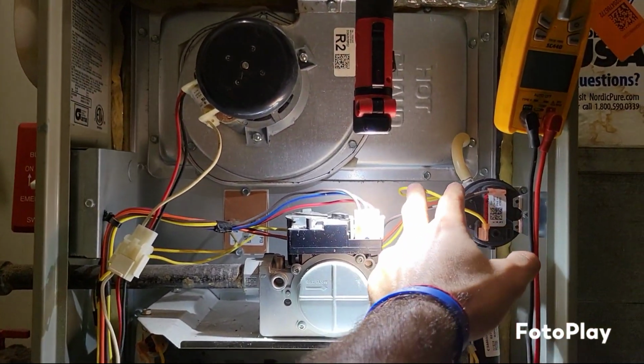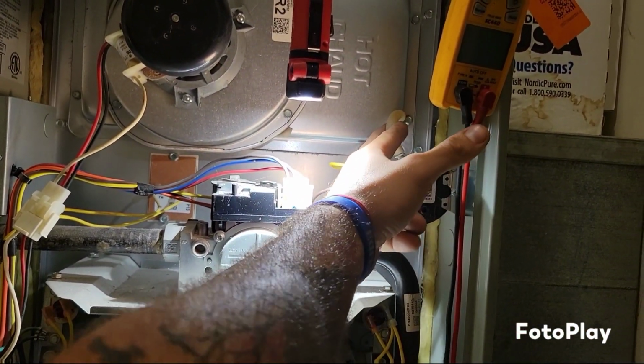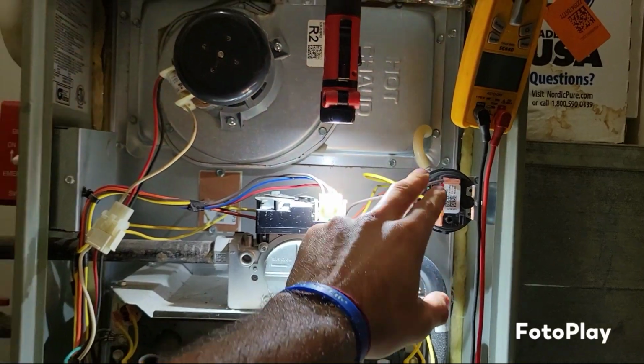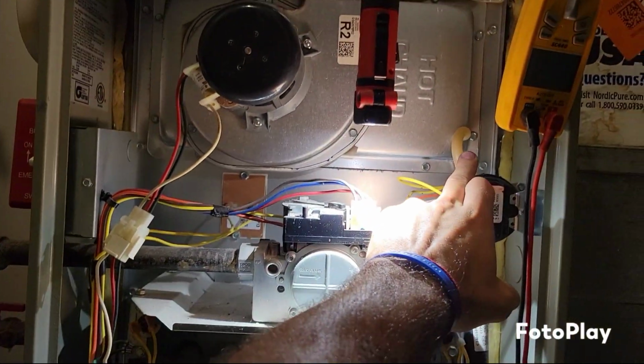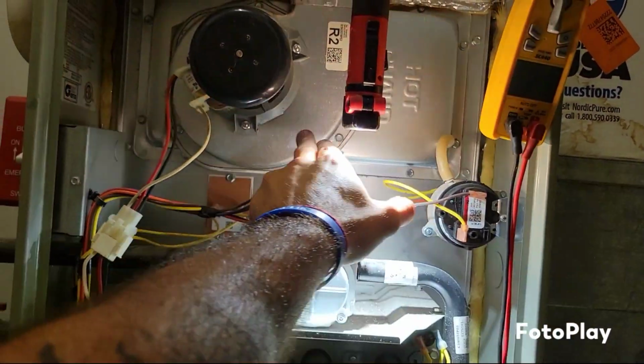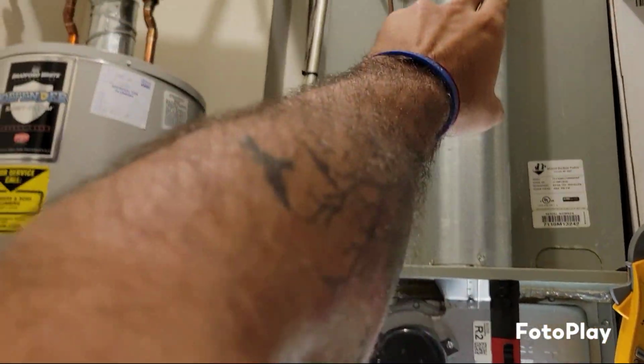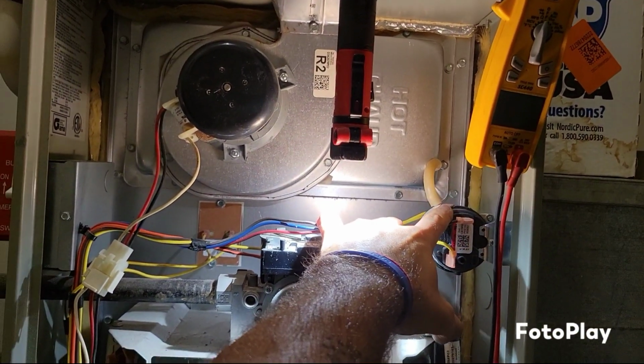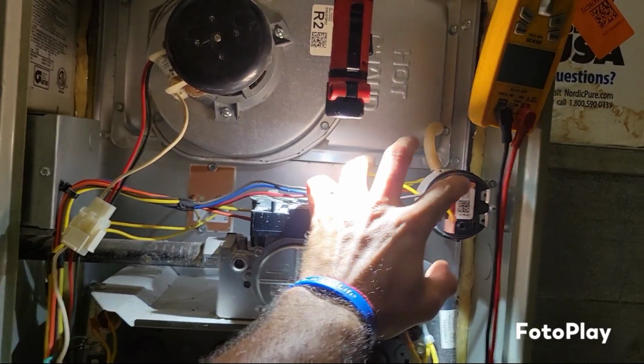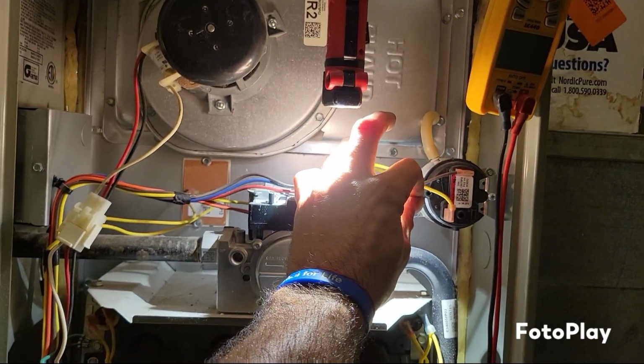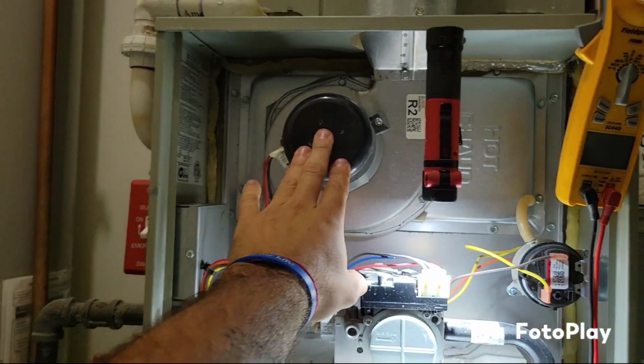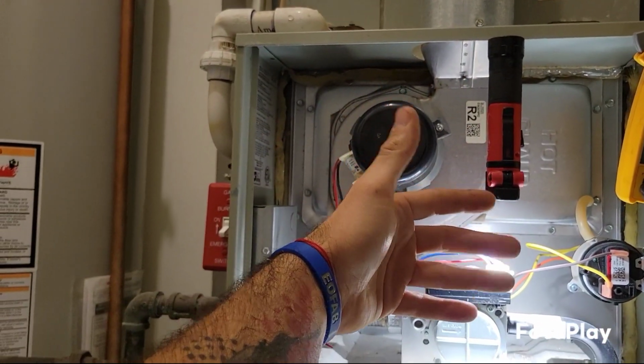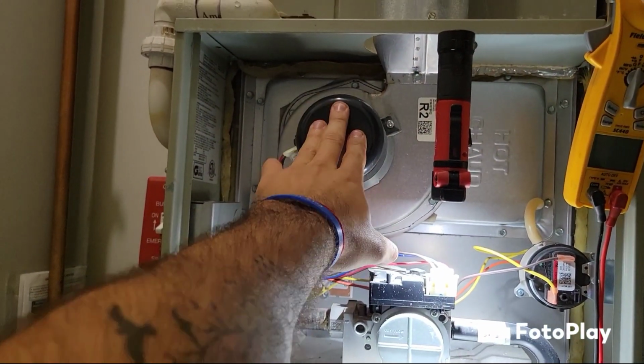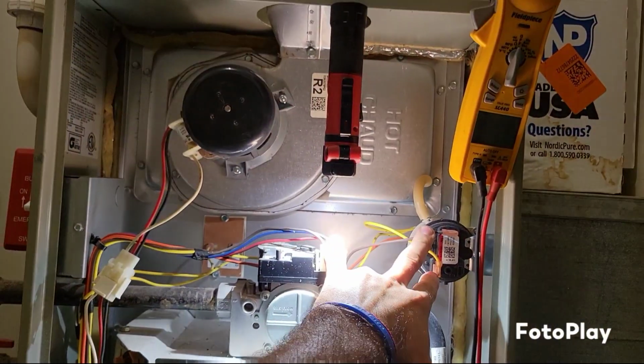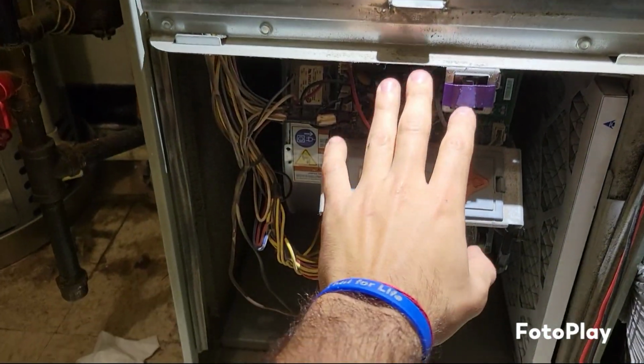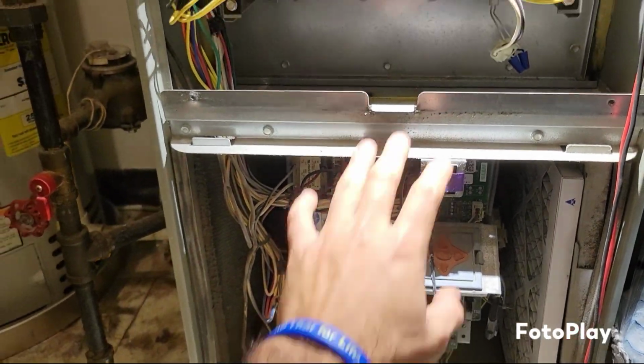So essentially we are pulling air through here, and that is going to close the switch. So think about it, air is being pulled from this hose inwards, goes into the motor, comes out the flue. So when this gets pulled in, this switch closes. So it creates a contact between these two points, and it closes that contact, saying that, hey, my motor's running, now we can continue on with our heating cycle. If the motor was not running, or there was an issue with the motor, this will obviously not close, thus giving us the error code that we see down here. Now this happened multiple times.